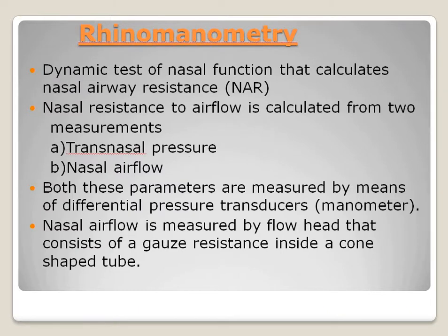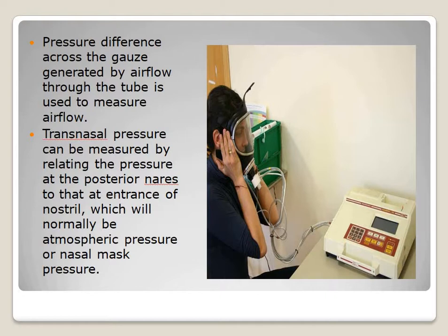Rhinomanometry is a dynamic test of nasal function that calculates nasal airway resistance. Nasal resistance to airflow is calculated from two measurements: transnasal pressure and nasal airflow. Both parameters are measured by differential pressure transducers. Nasal airflow is measured by a flow head consisting of a gauze resistance inside a cone-shaped tube; the pressure difference across the gauze generated by airflow through the tube is used to measure the airflow.